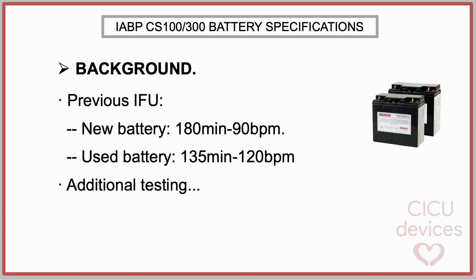The CS100 and CS300 consoles are equipped with sealed, maintenance-free lead-acid batteries, designed primarily to provide power during transport or temporary loss of AC power. Previously, the instructions for use stated that a new battery could provide approximately 180 minutes of runtime at 90 beats per minute, while a used battery was specified to deliver a minimum of 135 minutes at 120 beats per minute.